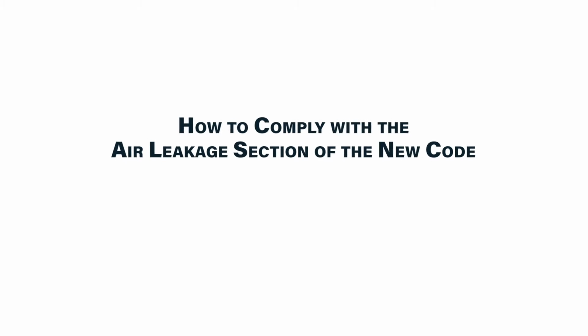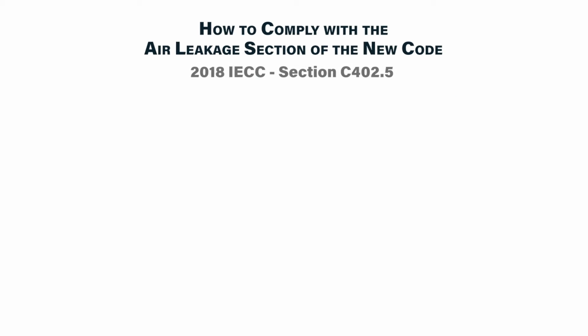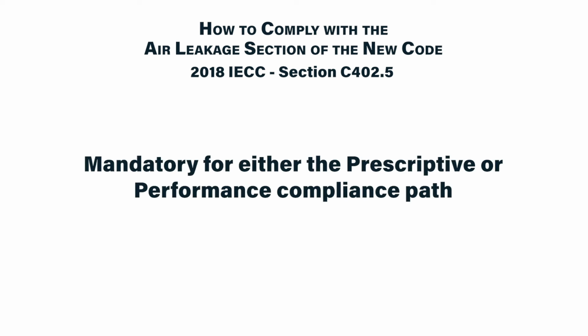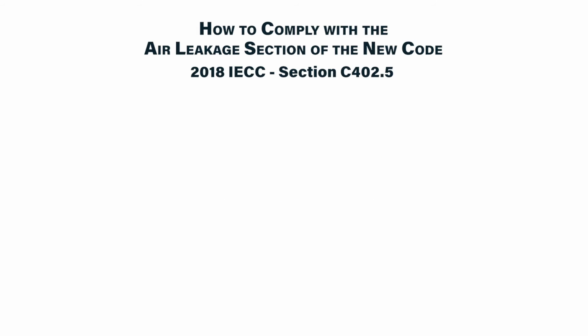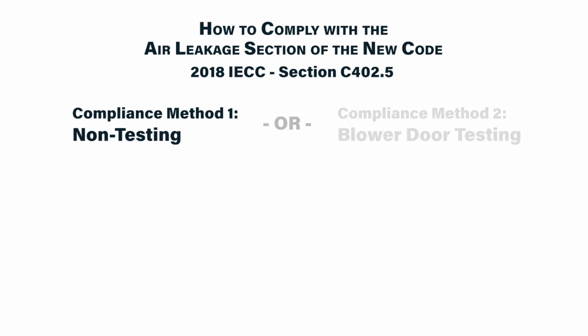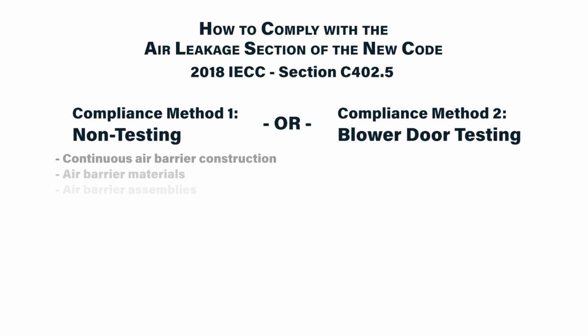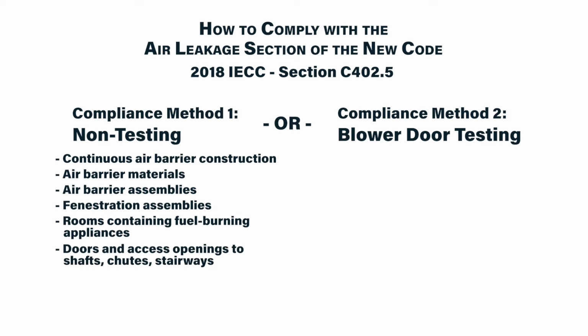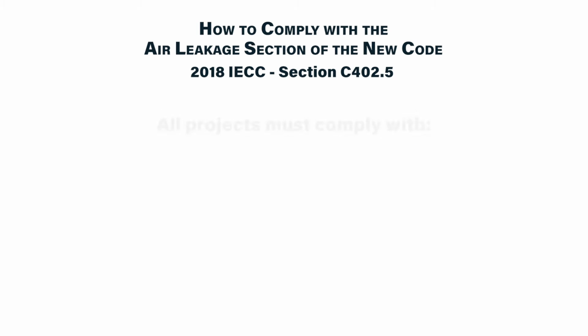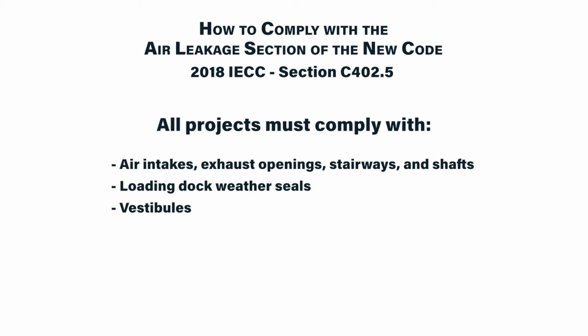Now that you understand what air leakage is and the importance of reducing it, I will now go over the code requirements for air leakage, Section C402.5 of IECC 2018. This section is mandatory for all projects, regardless of prescriptive or performance compliance path. There are two different ways to comply with this section. One is the non-testing method, which requires compliance with several items. The other requires blower door testing. Regardless of testing or non-testing method, all projects must comply with a few mandatory items, as shown on the screen here.